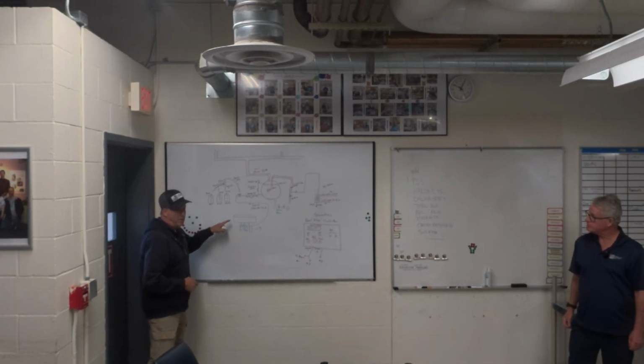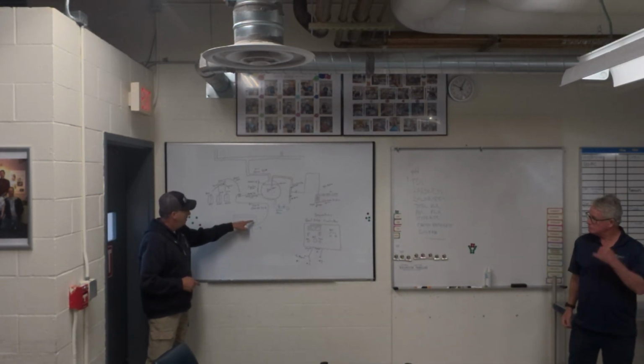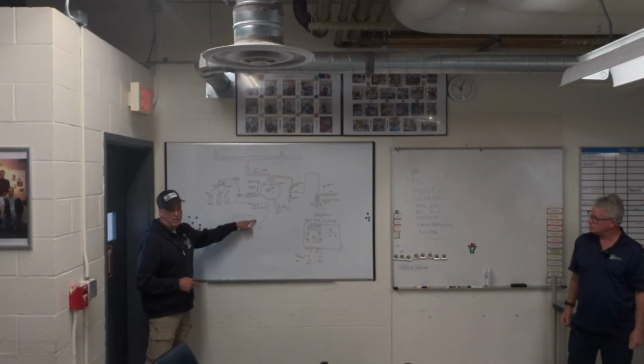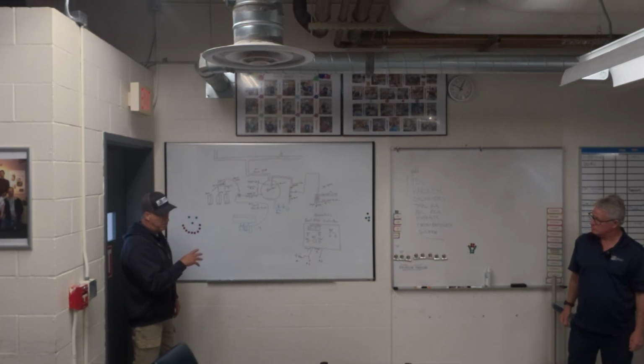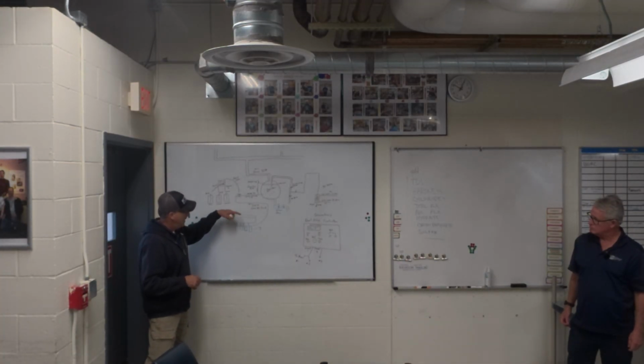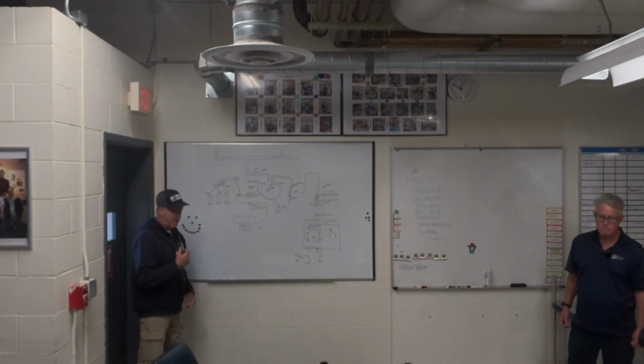We failed to mention that we also add chemical OX21 right to the DA tank proper. The DA tank's mission is to preheat the water coming from ML1 and allow it to outgas, preheat it, put a little bit of pressure cap on there, and there's a sparge tube in there. There's a whole discussion about the DA tank, but we add a little OX21 to pre-treat it, to scavenge any oxygen.